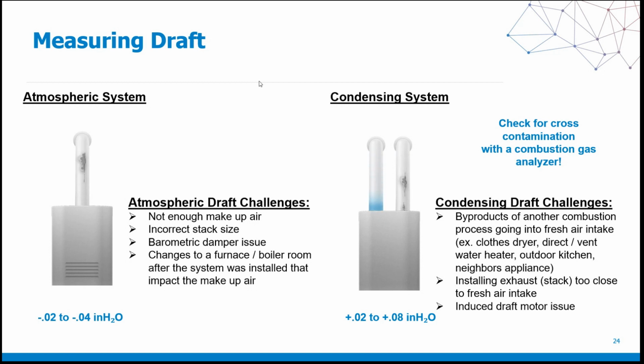And things that can impact an atmospheric system are if somebody replaced the stack or the exhaust with an incorrect size piece of pipe, that can impact the velocity and the way that the flue gases are actually exiting or leaving. If you have a barometric damper that is hung up or misbehaving, that can create a problem as well, because those flue gases are not going to exit properly and backdraft down into the system itself.